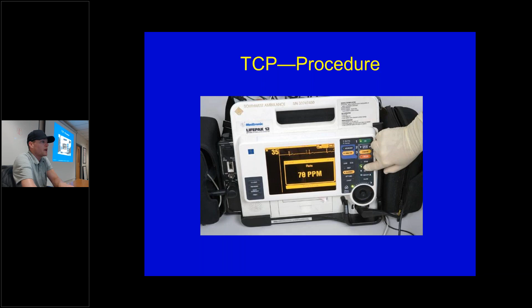So yeah, you're designating the rate. It usually should be anywhere between 60 and 80. You generally don't want to go above 80. So after you've got the rate, then you can start it, right? You can start the pacemaker, and then you increase the current after you've already started it. So it's starting to give current at the rate that you set it.